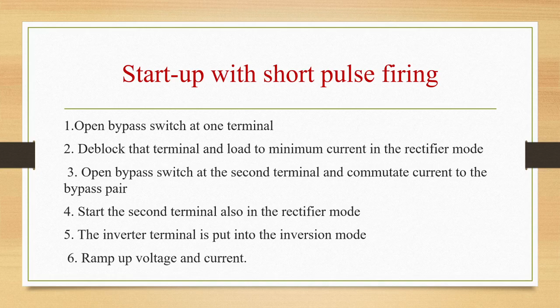First, open the bypass switch at one terminal. Second, deblock the terminal and load to minimum current in the rectifier mode. Third, open the bypass switch at the second terminal and commutate current to the bypass pair. Fourth, start the second terminal also in the rectifier mode. Fifth, the inverter terminal is put into the inversion mode. Sixth, ramp up voltage and current.